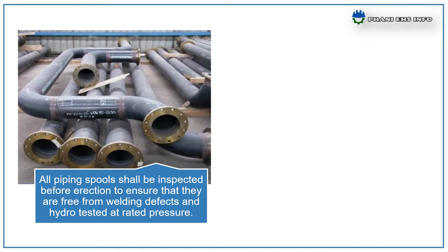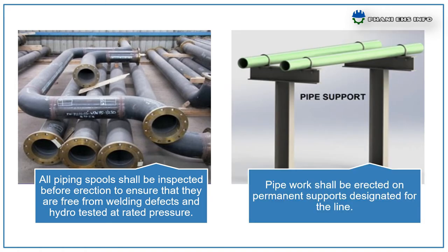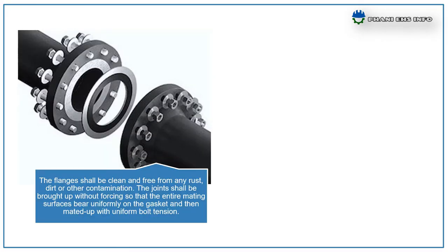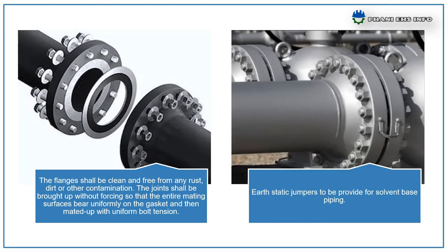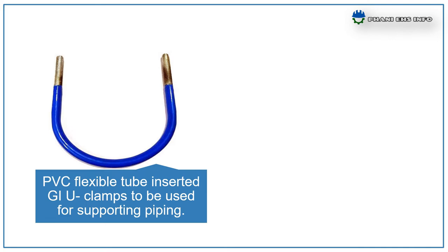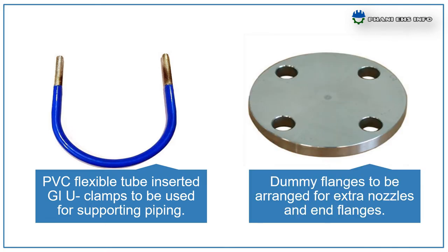All piping spools shall be inspected before erection to ensure they are free from welding defects, hydro-tested, and at the correct pressure. Pipework shall be erected on the permanent supports designated for the line. Flanges shall be clean and free from any rust, dirt, or other contamination. Joints shall be brought up without forcing so that the entire mating surfaces bear uniformly on the gasket and torqued up with uniform bolt tension. Electrostatic jumpers to be provided for solvent-based pipe. PVC flexible tube-inserted GI U-clamps to be used for supporting piping.